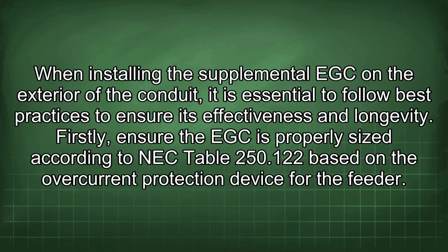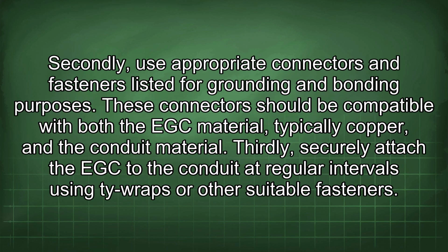When installing the supplemental EGC on the exterior of the conduit, it is essential to follow best practices to ensure its effectiveness and longevity. Firstly, ensure the EGC is properly sized according to NEC Table 250.122 based on the overcurrent protection device for the feeder. Secondly, use appropriate connectors and fasteners listed for grounding and bonding purposes. These connectors should be compatible with both the EGC material, typically copper, and the conduit material.